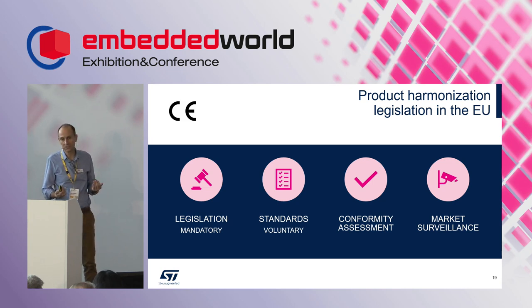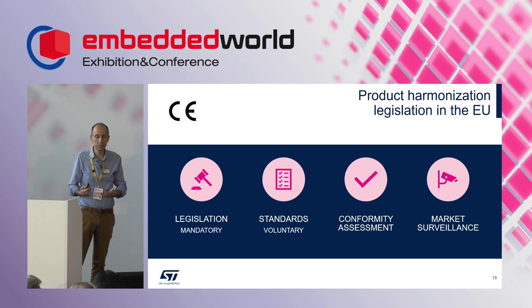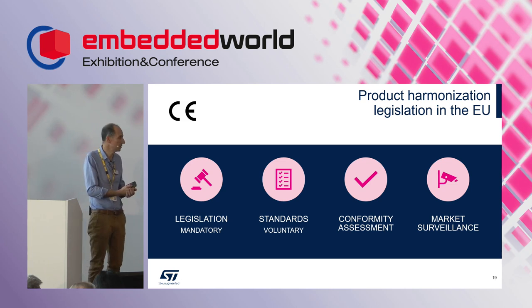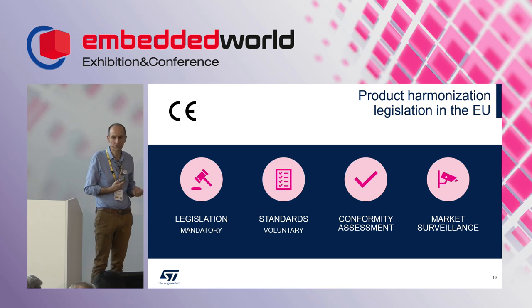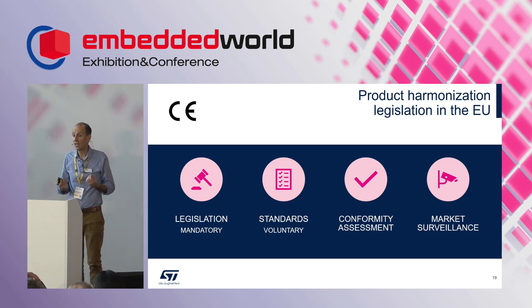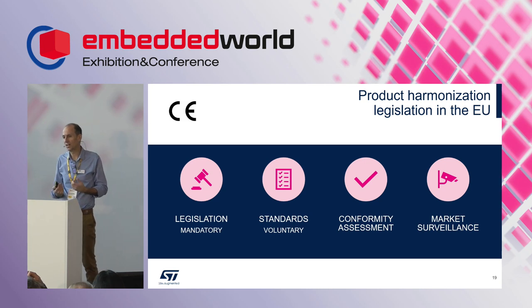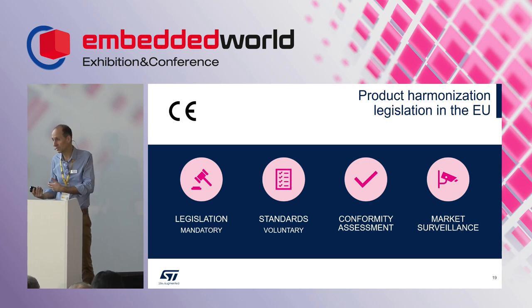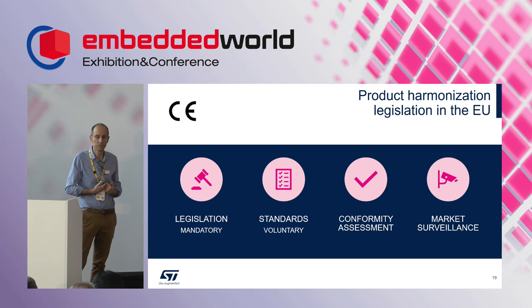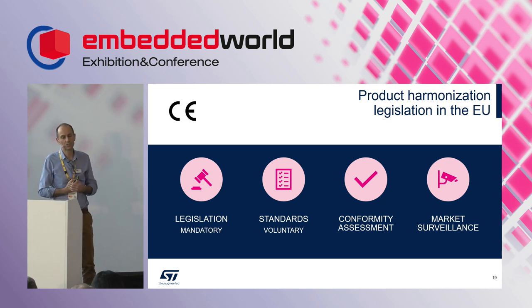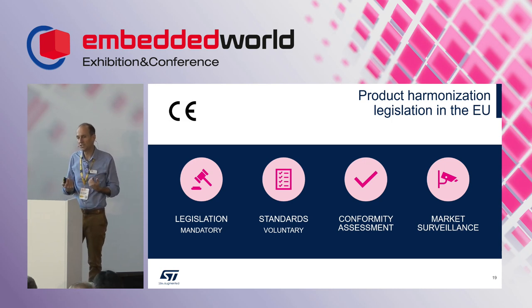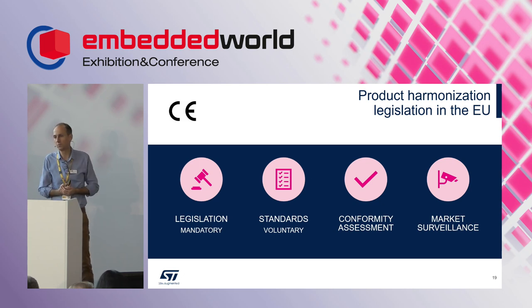Second point is conformity assessment, done either internally or by a notified body. The last aspect is market surveillance: device makers need to keep a close watch on how the regulation evolves once applied—it's not just about placing products on the market, but looking at the legal obligations for the sold product. On top of this, the CE mark is really important; everyone knows it, but for radio products, to get the CE mark the product has to conform to the RED requirements.